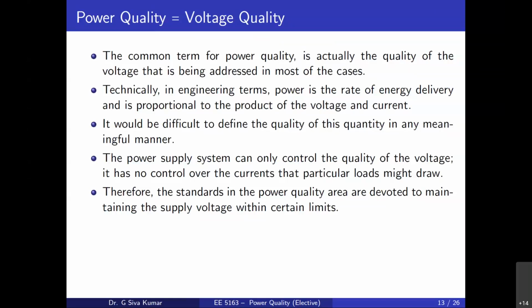The power supply of a system can only control the quality of the voltage. It has no control over the currents that particular loads might draw. The current drawn by the load is not dependent on the utility's control. The only thing the utility can control is to improve the quality of the voltage.